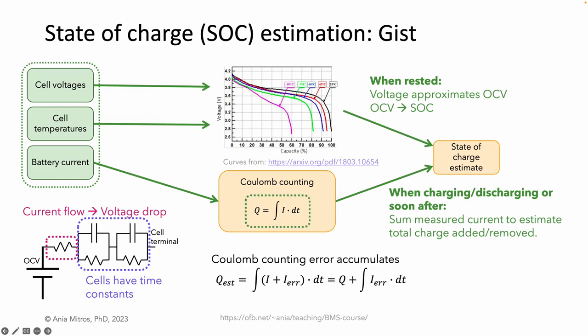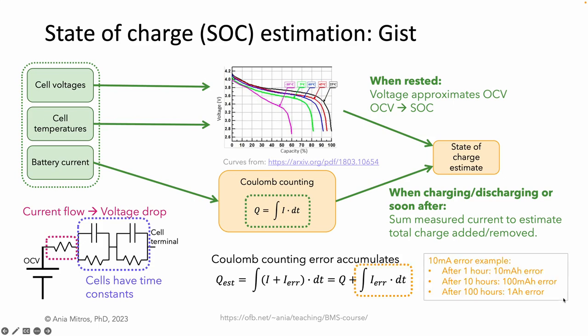The trouble with Coulomb counting is that any measurement offset error is accumulated. Say we have a 10 milliamp measurement error. After an hour, we will have a 10 milliamp hour error in our state of charge estimate. After 10 hours, we'll have a 100 milliamp hour error. After 100 hours, we'll have a 1 amp hour error. The integrated error just keeps growing, as you'd expect from integrating a constant.